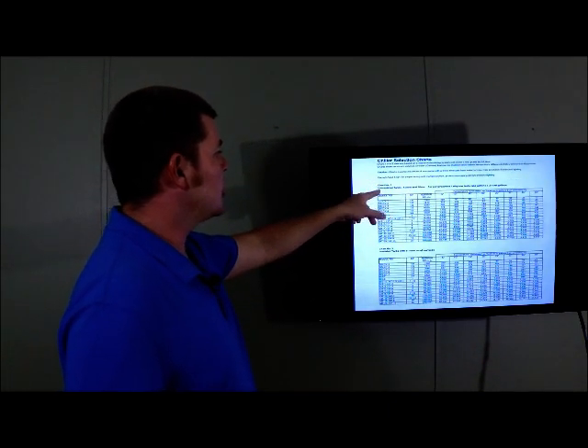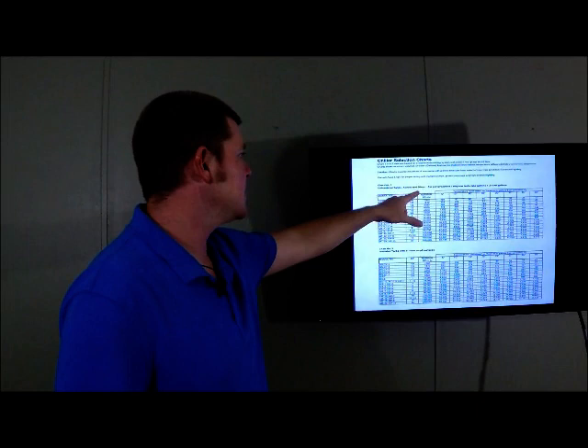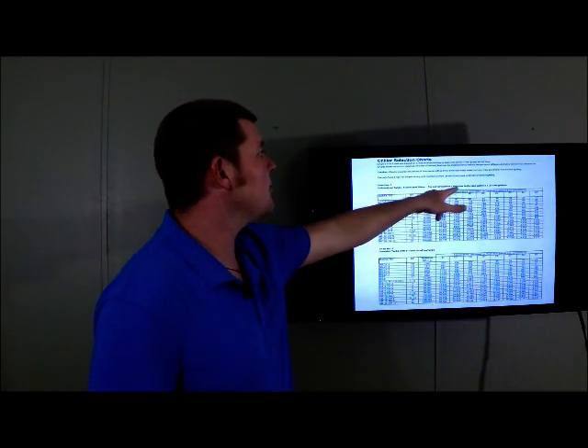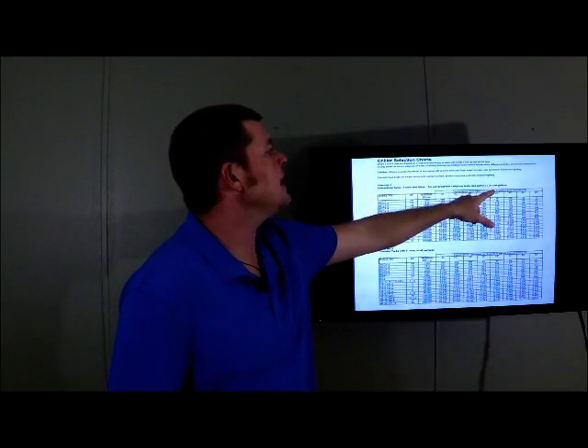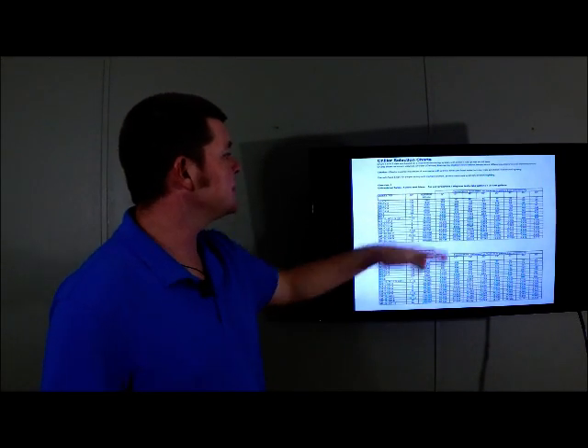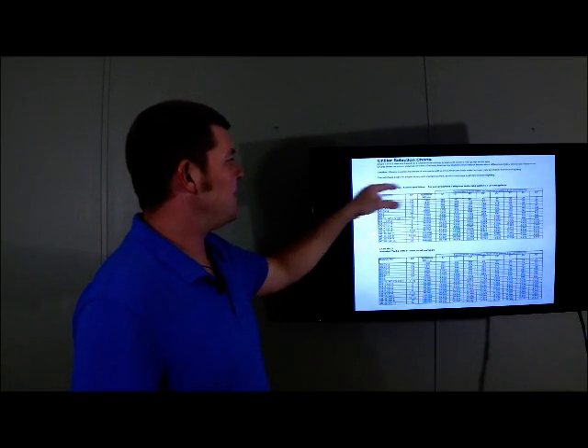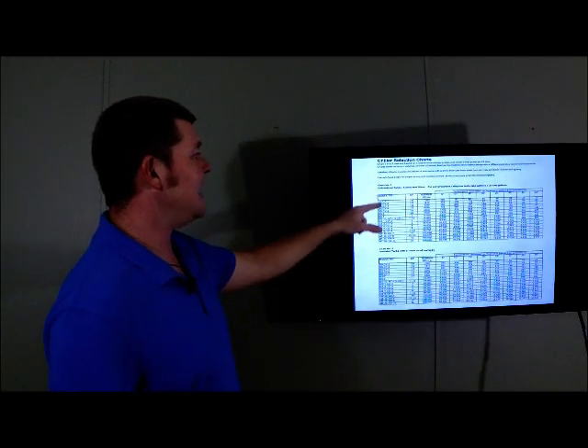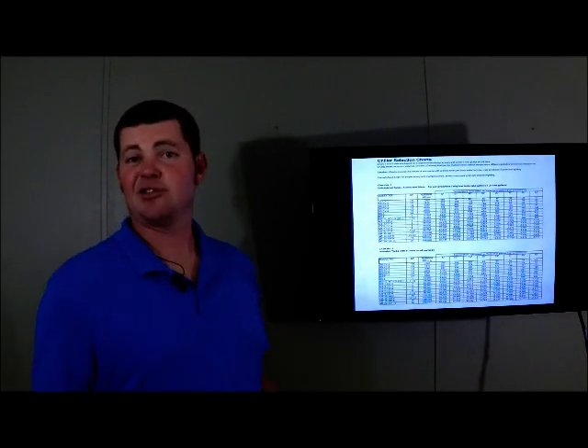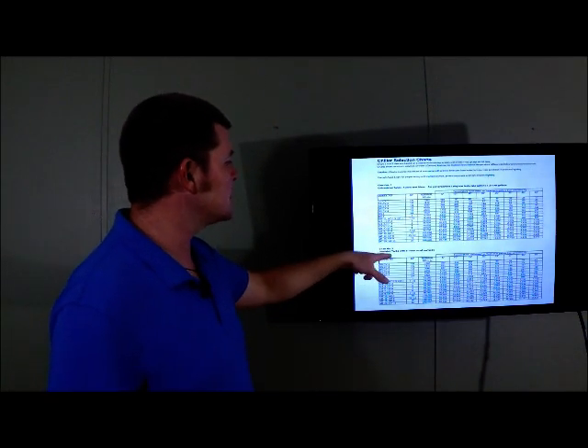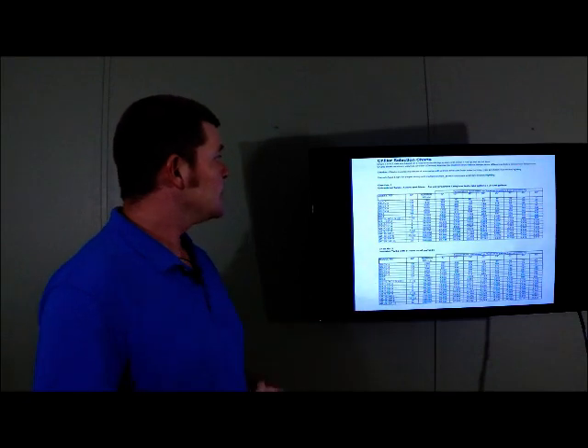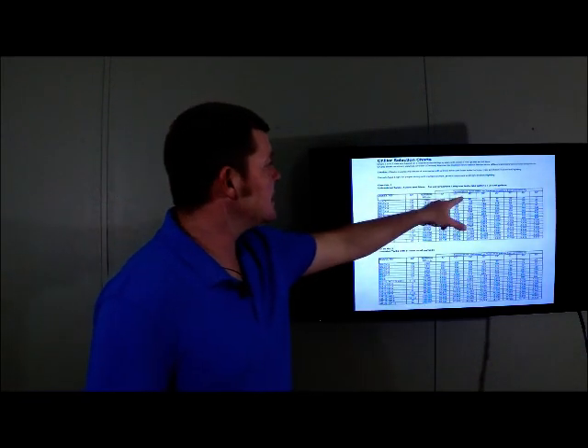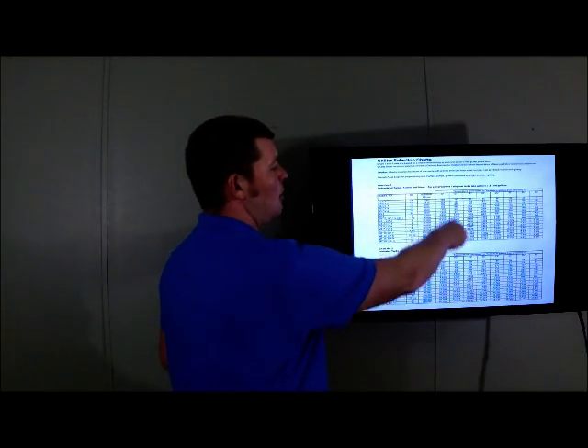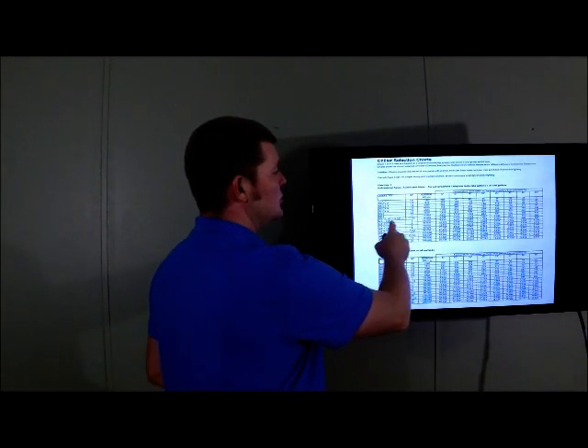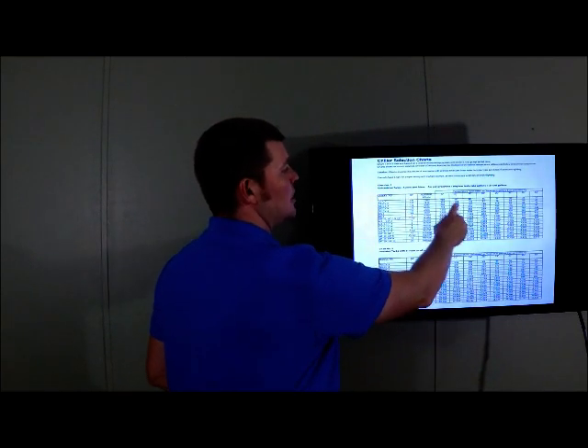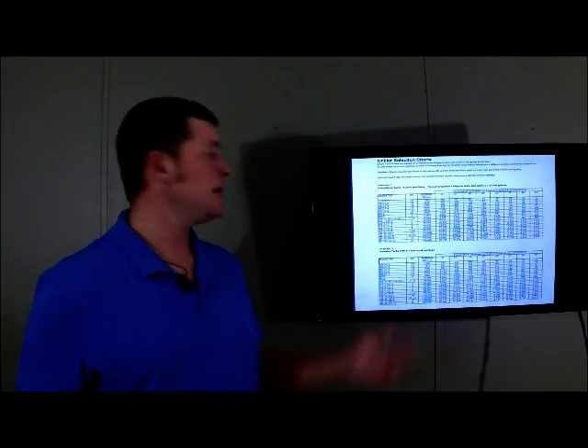They actually tell you right here, chart number 1, uninsulated tanks, acrylic and glass. So kind of more like a fish tank. For polypropylene or polyethylene tanks, take the gallons times 0.8, so 80% of the gallons here, and that's your net gallons. So it tells you this is just for uninsulated tanks. If it's a poly tank like I have here at the farm, it's actually 80% of the value of the gallons here, because they're less insulated. And then down here is a whole chart for insulated tanks with 2-inch foam on all surfaces. So this, again, allows you 5 degrees, 10 degrees, 15, 20. You can stare right here and model which model is going to chill, and it has the horsepower, which model is going to chill at what temperature, how much of a drop down you want, and how many gallons you need.